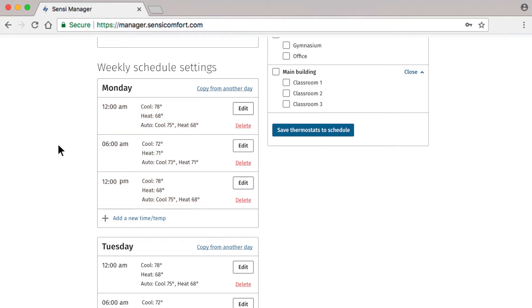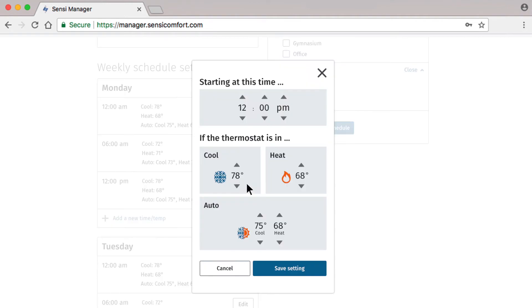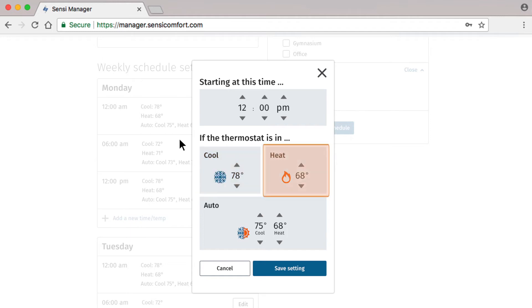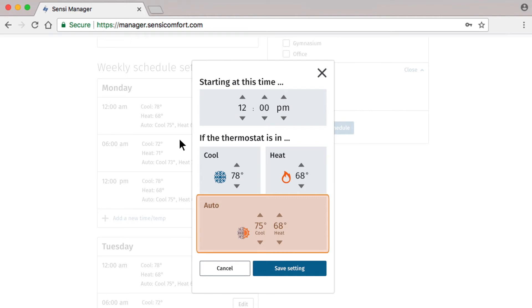Let's edit our new schedule starting with Monday at 12 p.m. When we click Edit, we see options to change the start time and temperature settings under all three HVAC modes. In this example, when in Cool Mode, our system will begin cooling the building when the temperature exceeds 78 degrees. When in Heat Mode, it will begin heating the building when the temperature drops below 68 degrees. And when in Auto Mode, the temperature range will be between 75 and 68 degrees.